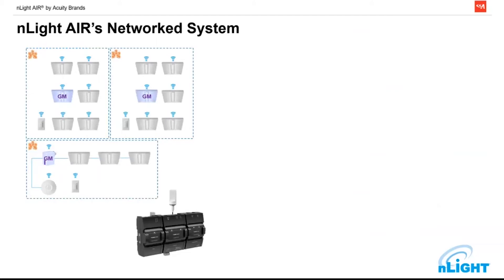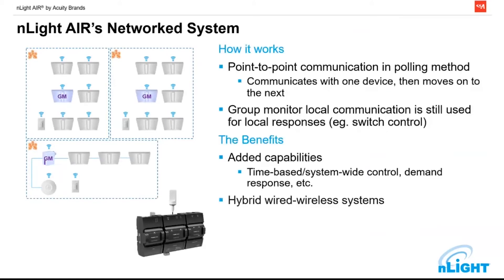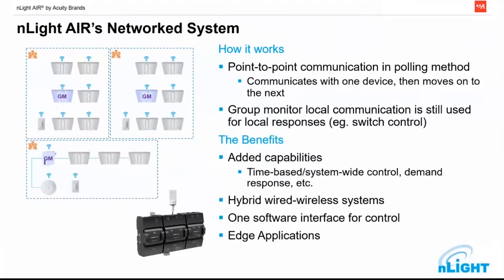This explains how we use a combination of different devices, bringing in our wireless Eclipse with a wireless antenna. What is very interesting is the group monitor — this purple GM device. Each individual light fixture might be a wireless beacon communicating with the rest, but when commissioning, only one light fixture needs to have communication back to the home run. That group monitor gets data from a phone, an Eclipse device, or an iPad and sends it out to all the others in the space. So if the space becomes an issue, we need one fixture close enough and then branch out from there as a beacon to broadcast to all of the others.